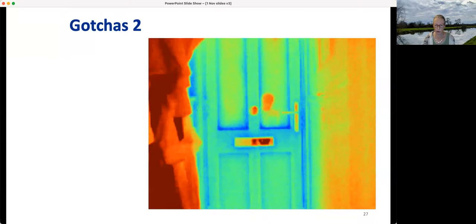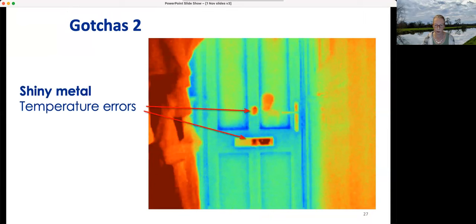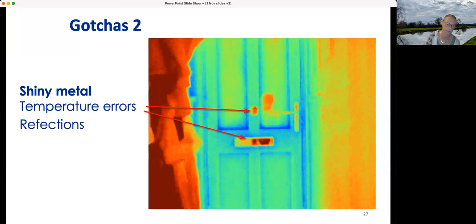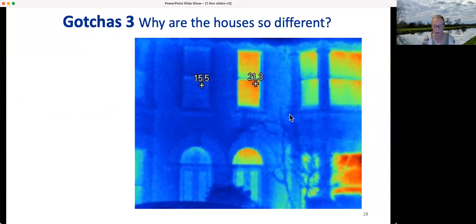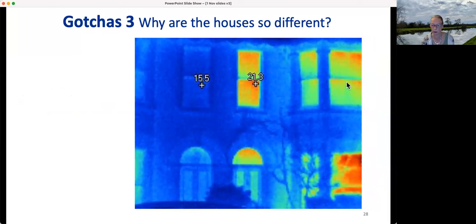Here's a door that's partly wooden and partly metal. This area here is classically hot — but if you step to one side, you'll find it is a reflection of you. We're looking at two different houses here: one on the left is cold and the one on the right is apparently warm, with windows seeming to leak heat. What might be the cause? One has heating on, the other doesn't — it's either unoccupied or unheated.